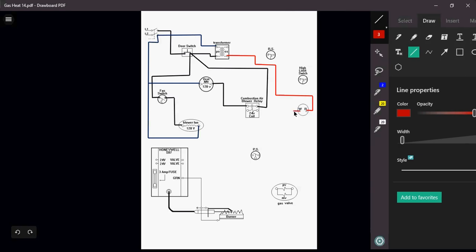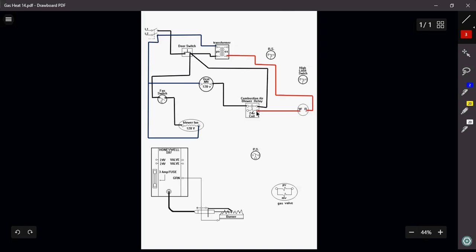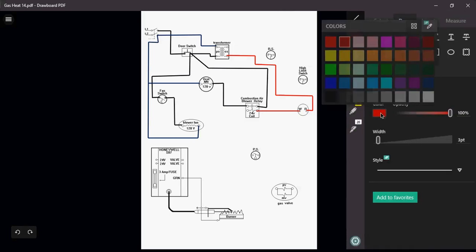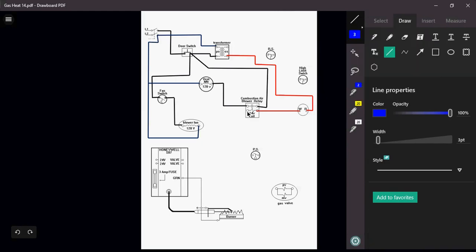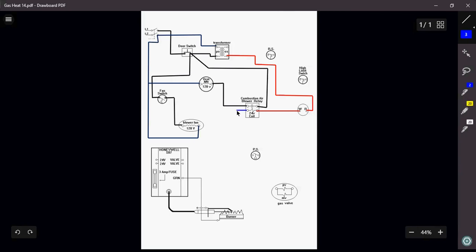Okay, so to do that, I'm just going to use a different color, red. Okay, so I'm going to come out, and I am going to wire in my 24 volt coil. Out of my 24 volt coil, I'm going to go right back up to my transformer, my common on my transformer. Okay, now when dealing with commons off of your transformer, they could be different colors. Okay, sometimes they're blue, sometimes it's black, sometimes it's some color. Okay, so what you have to physically do is you're going to have to look at that circuit to see where your common actually is.